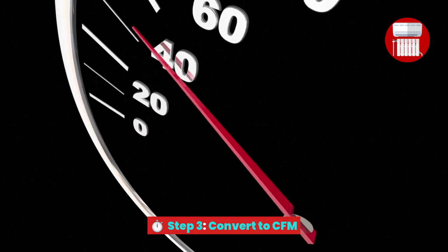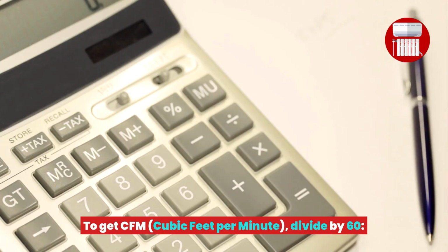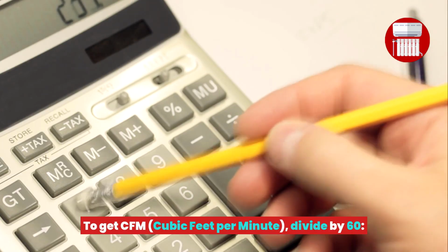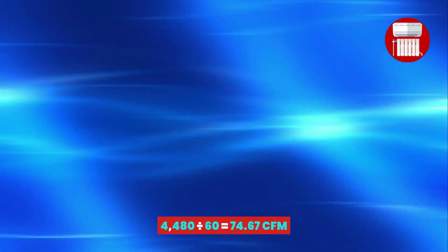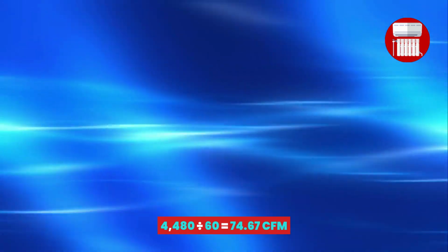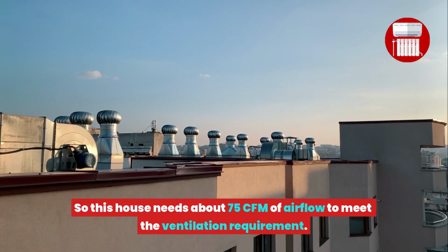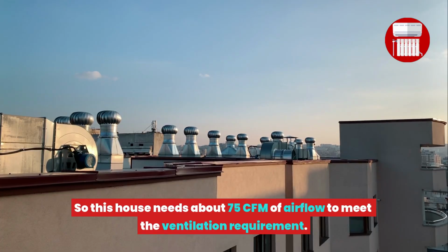Step 3. Convert to CFM. To get CFM, cubic feet per minute, divide by 60. 4,480 divided by 60 equals 74.67 CFM. So this house needs about 75 CFM of airflow to meet the ventilation requirement.